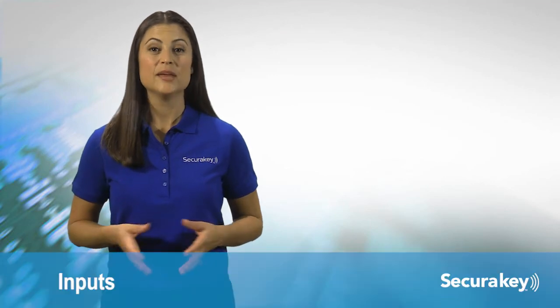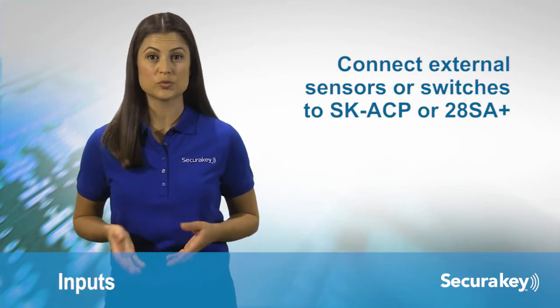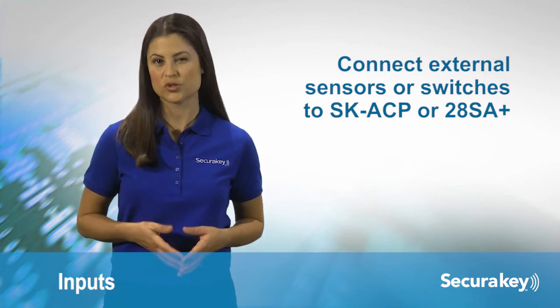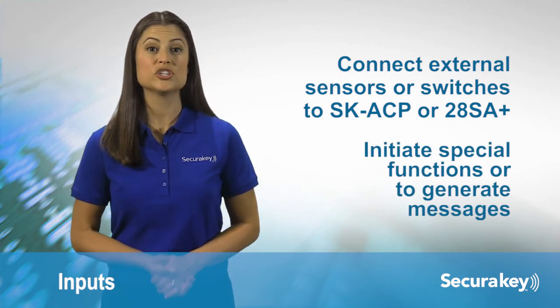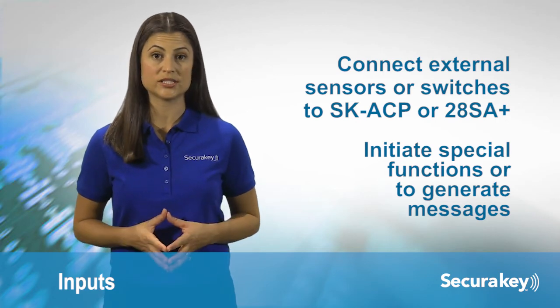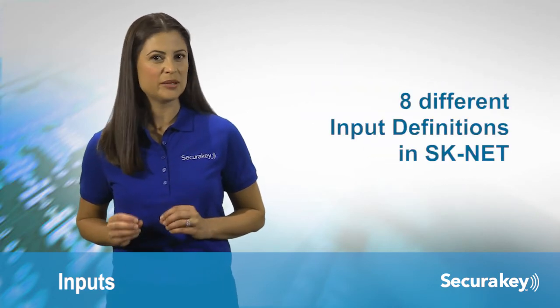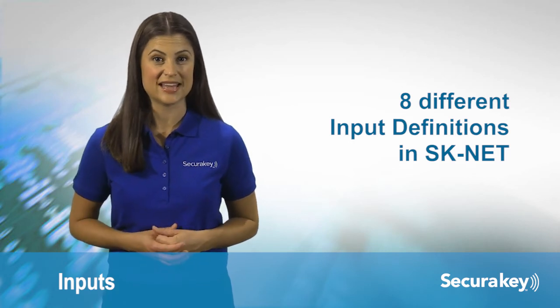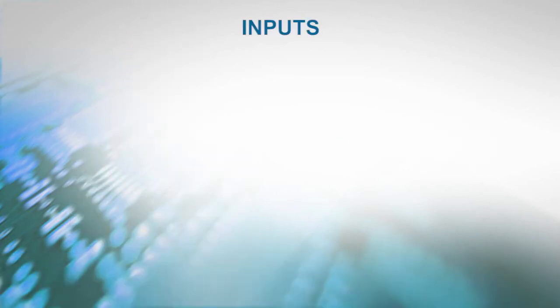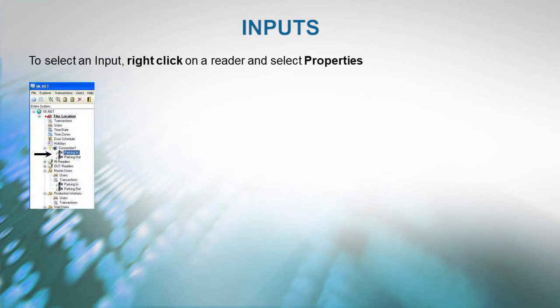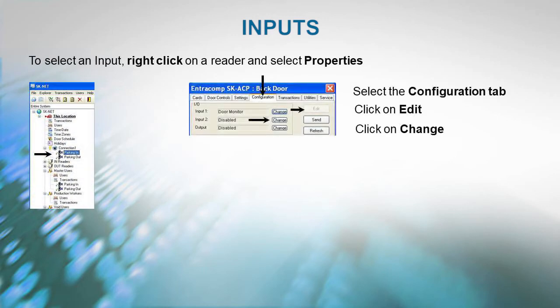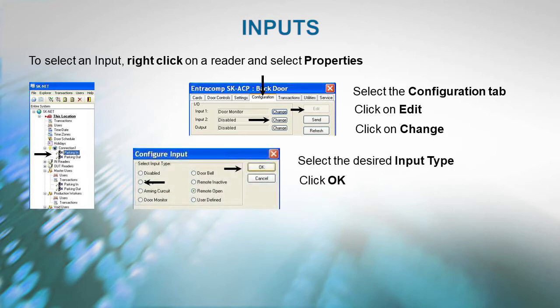Inputs. Inputs are circuits that connect external sensors or switches to an SK-ACP or 28SA+. They are used to initiate special functions or to generate messages and transactions. There are 8 different input definitions you can choose in SKNet. To select an input, right-click on a reader and select Properties. Select the Configuration tab, click on Edit, click on Change, select the desired input type, click OK, then Send to the reader.